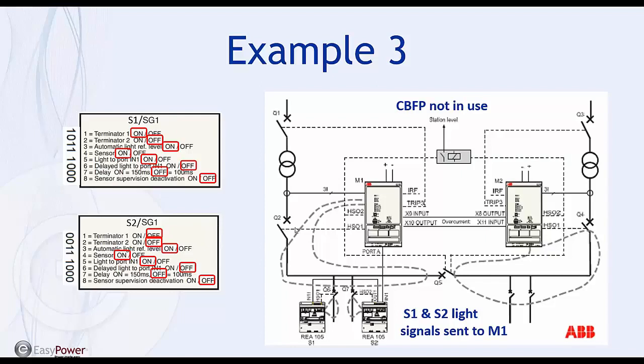So if somebody's exposed there, you're going to have some buildup of incident energy from that additional 100 milliseconds. And so it's something to keep in mind that at the expense of having breaker failure, you have more incident energy.